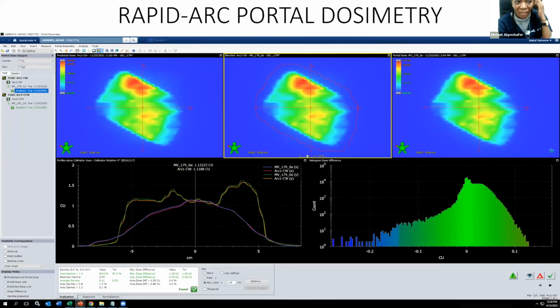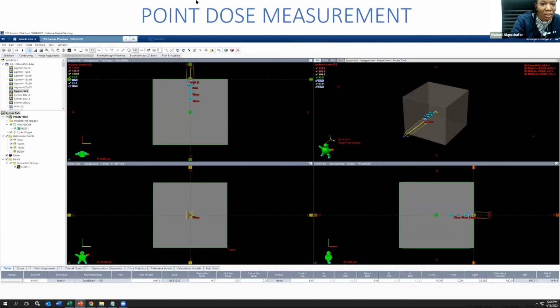Okay, so after the commissioning of the TPS, we need to do verification also. There are some steps that we carried out, like the point dose and the end-to-end testing. All these are to verify the accuracy of the commissioning of the treatment planning system. The point dose measurement is just trying to get the absorbed dose at different points in the target, so that I would be able to compare the measured dose with that of the TPS commissioning.